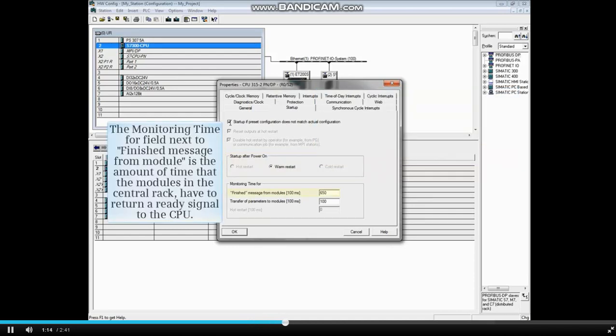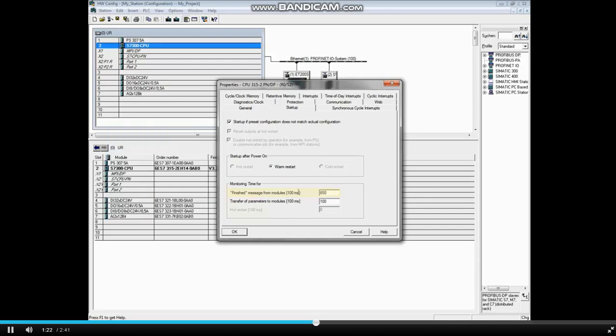The monitoring time field next to Finished message from module is the amount of time that the modules in the central rack have to return a ready signal to the CPU.